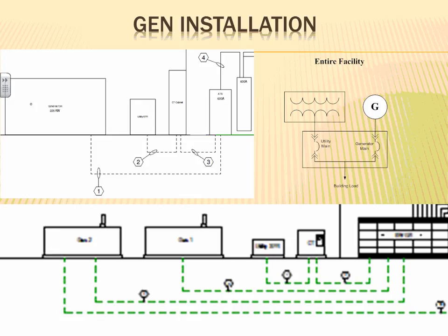Now, if you have a 500 kW generator and you have a molded case circuit breaker, and you're going to use thermomagnetic circuit breakers, you've got to be very careful when you coordinate with these. Yep, absolutely. I should have thrown one of these in too. You might have to change the type of the circuit breaker. If you have an adjustable instantaneous circuit breaker, even molded case circuit breakers, you could get really good coordination with them, as long as the instantaneous is adjustable.